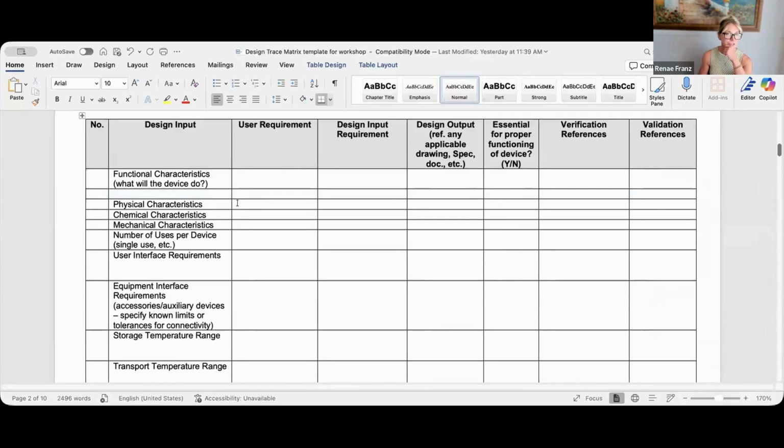What are the physical characteristics? So for this whole blood mixer at the time, they were just using what was called a trip scale. It kind of sat on the edge of a blood donor bag, so you didn't have to bend over very far. It was right there next to the donor, so you could mix the blood, hook the donor up to the blood bag, and disconnect them when they finished. But a little scale on the ground was a lot of movement for a phlebotomist, to have to go down there constantly and work and look at the scale, reconnect the donor.